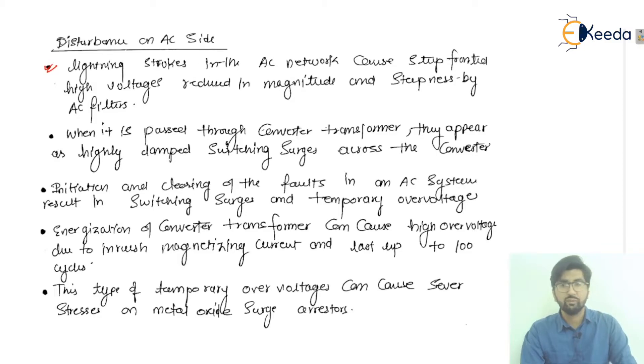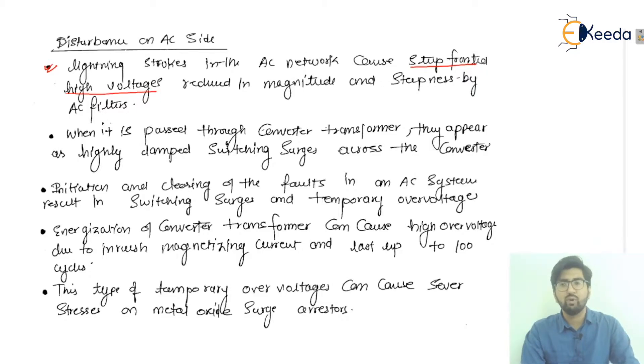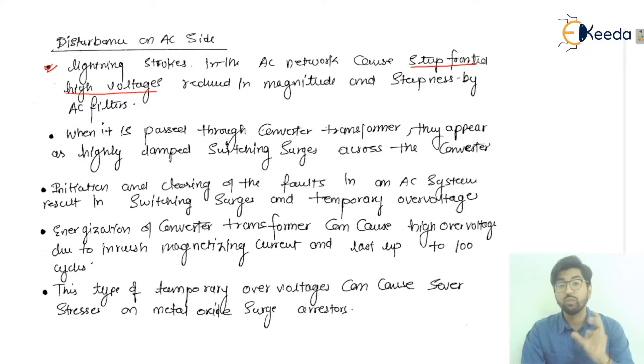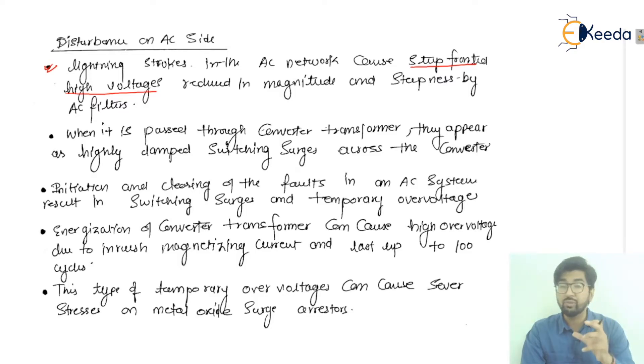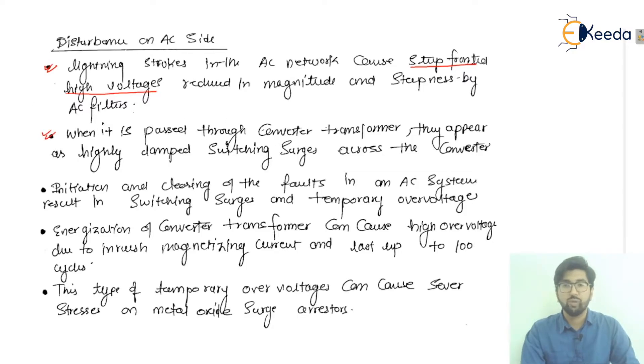In the AC network, lightning strokes may cause steep-fronted high voltages. The magnitude and steepness of these waves are reduced by the AC filters. Whenever lightning strokes occur, they appear as steep-fronted high voltage waves — an impulsive high voltage value for a short duration of time. The AC filters reduce both the magnitude and steepness of these steep-fronted high voltage waves.